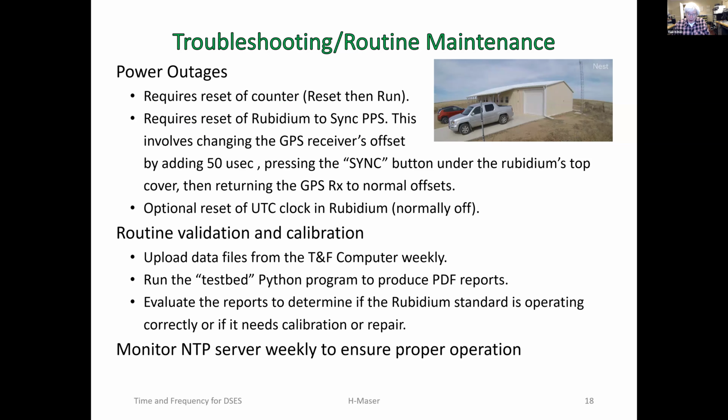Now, it doesn't require a genius, it just requires somebody to be at Haswell, and I can talk them through what buttons to push to do the resets. The resets are not necessary to get things up and running in terms of precision, time, and frequency, but they are necessary for the measurement that allows us to know if everything's working correctly. So this is one of the problems that we currently have, that power outages are not our friend.